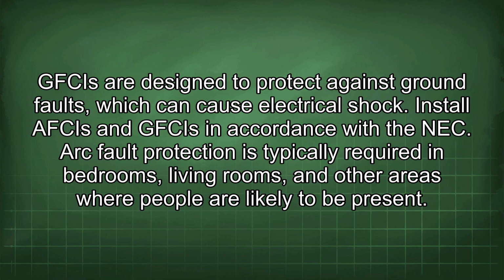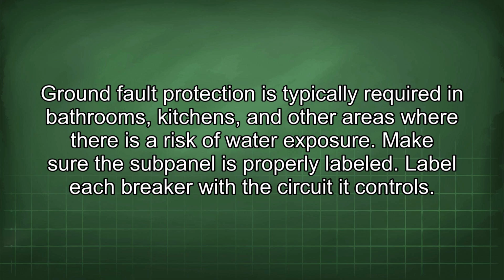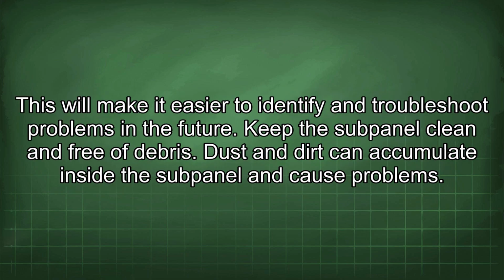Install AFCIs and GFCIs in accordance with the NEC. Arc fault protection is typically required in bedrooms, living rooms, and other areas where people are likely to be present. Ground fault protection is typically required in bathrooms, kitchens, and other areas where there is a risk of water exposure. Make sure the subpanel is properly labeled. Label each breaker with the circuit it controls. This will make it easier to identify and troubleshoot problems in the future.